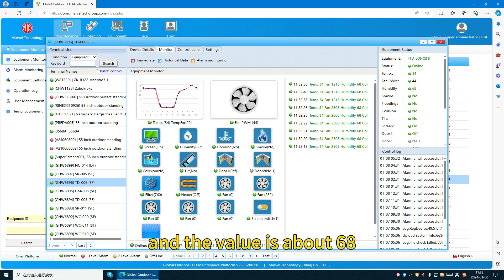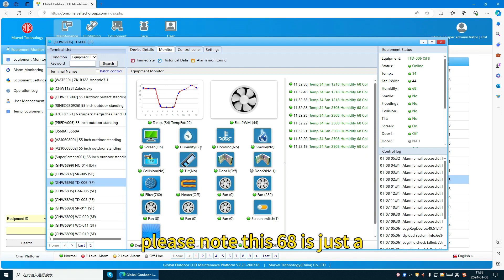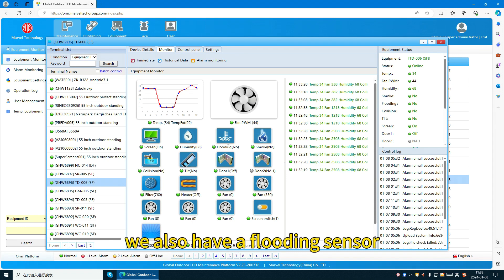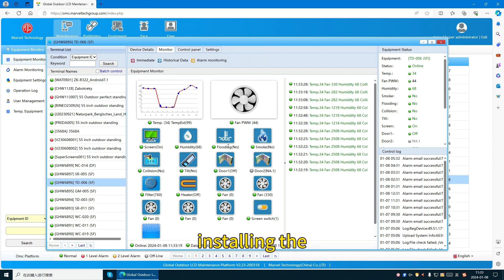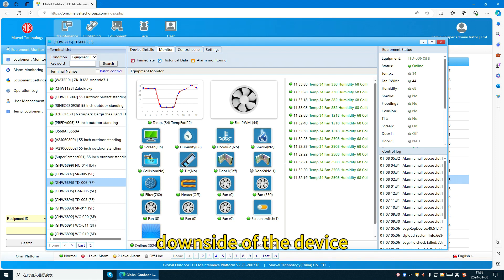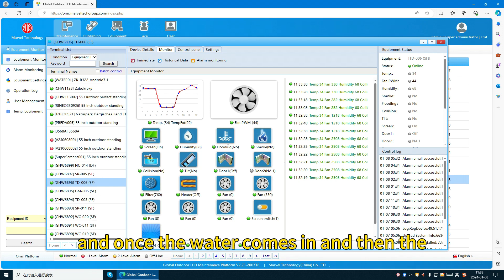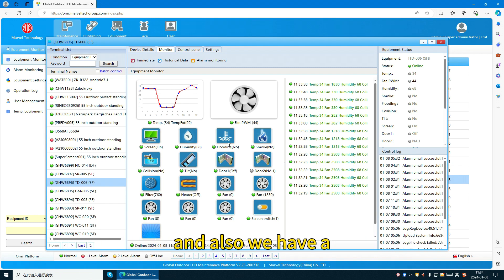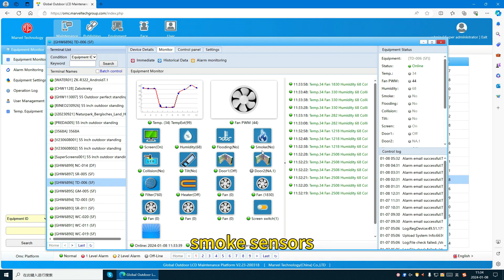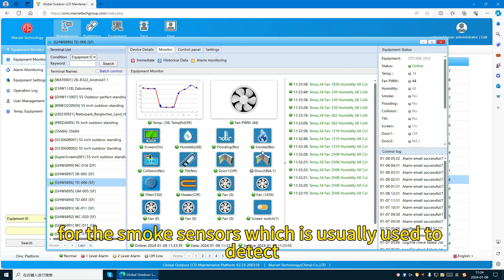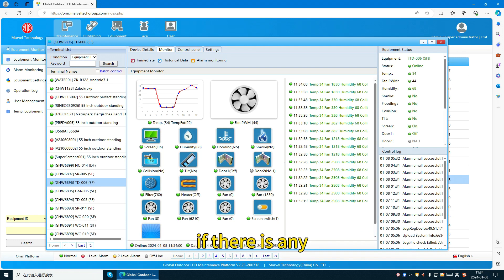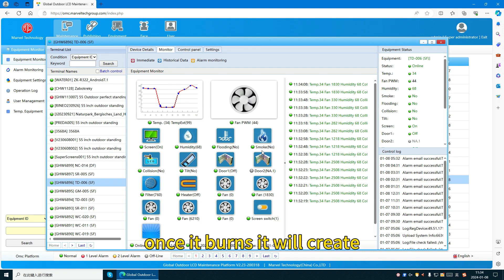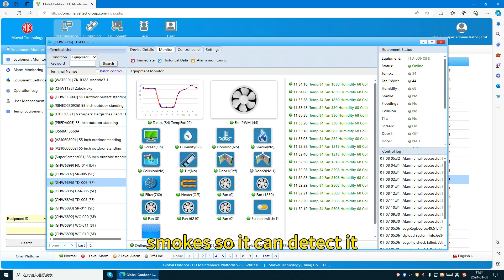The humidity value is about 68. Please note this 68 is just a monitor value — it's not the real value of the current air. We also have a flooding sensor, which is installed at the downside of the device. Once water comes in, the flood sensor will detect it. We also have smoke sensors, which are used to detect if there is any power board or material in a burn condition — once it burns, it will create smoke and the sensor can detect it.